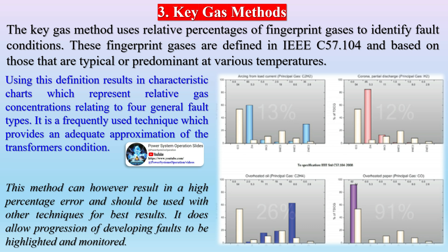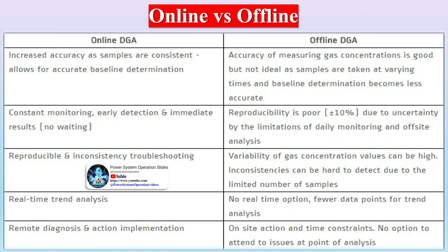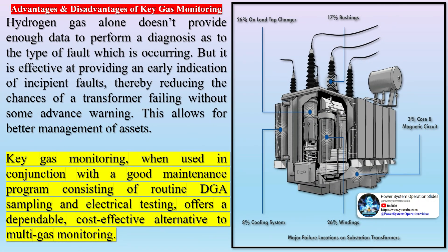The key gas method uses relative percentages of fingerprint gases to identify fault conditions. These fingerprint gases are defined in IEEE C57.104 and are based on those that are typical or predominant at various temperatures. Using this definition results in characteristic charts which represent relative gas concentrations relating to four general fault types. It is a frequently used technique which provides an adequate approximation of the transformer's condition, though it can result in a high percentage error and should be used with other techniques for best results.